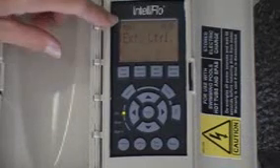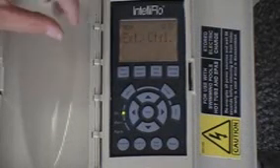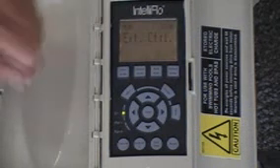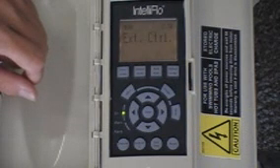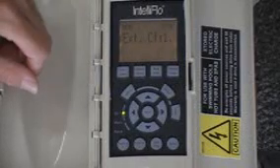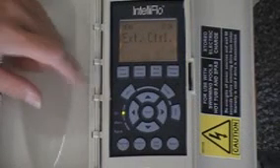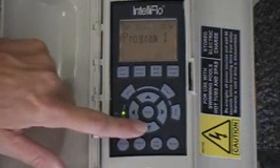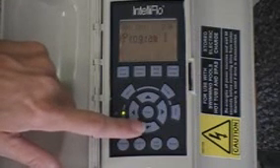So what we've done is we have a special menu in here that tells this pump that you've connected it to that other brand automation. And what you do is you would get into external controls. The IntelliCom box would be wired up to your automation, and then you would hit select, and you have four programs. You have four possible speeds of this pump to run.